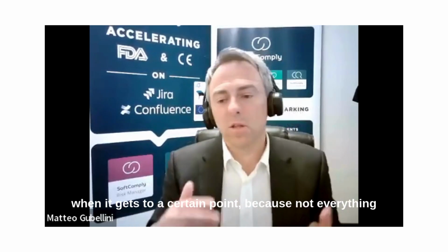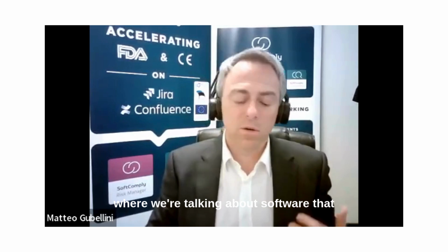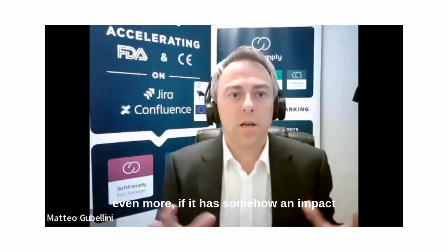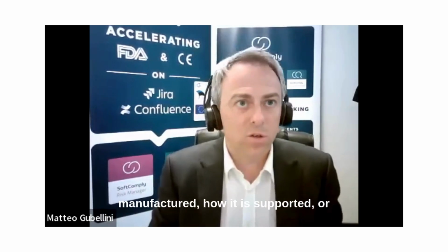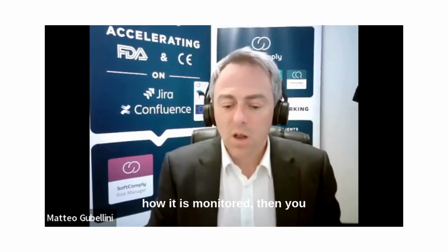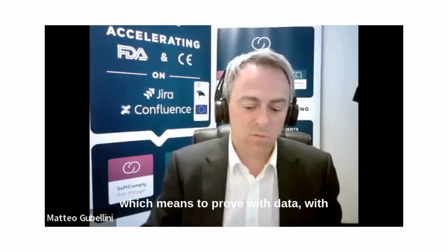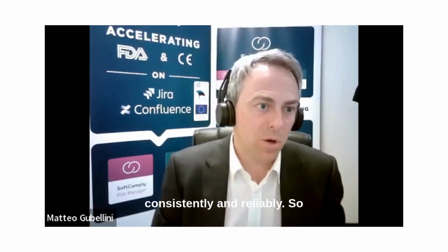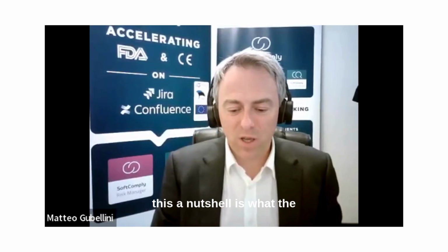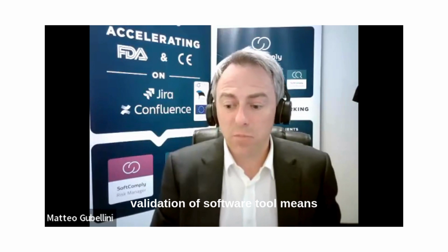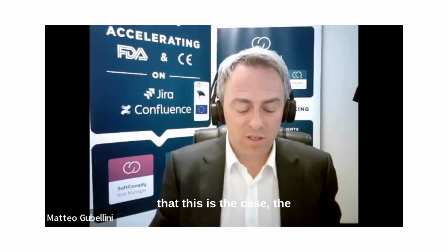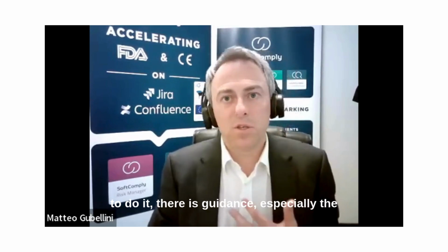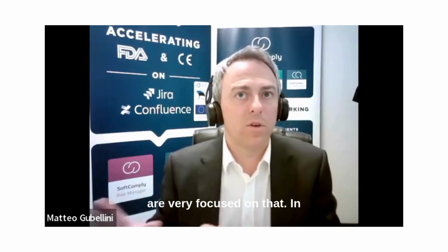So when it gets to a certain point, because not everything is critical, when it gets to a certain point where we're talking about software that manages documents, electronic signature, or even more, if it has somehow an impact on the product in terms of how it is developed, how it is manufactured, how it is supported, or how it is monitored, then you need to have a formal process to validate it, which means to prove with data, with objective evidence that it does what it is supposed to do consistently and reliably. So in a nutshell, this is what the validation of software tools means: provide evidence that this is the case. The extent of this validation, exactly how to do it, there is guidance, especially the FDA is more on the manufacturing process. They are very focused on that.